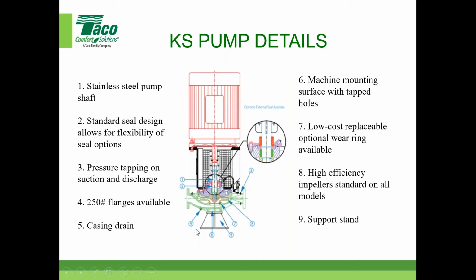And we do have support stands that you can add to your purchase order or specify, highly recommended once you start getting above maybe 20, 30 horsepower and it's going down onto the floor. You don't want to bolt this hard to the floor, and I'll talk about that from an installation standpoint.